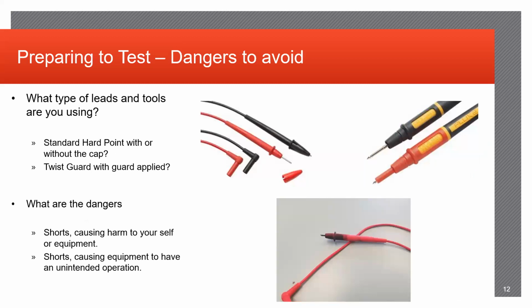Verifying correct test leads is important, especially when you're hooking up with your meter. The picture shown on the very right is a standard Fluke lead. The top black lead is actually much more dangerous than the bottom red lead, and the reason is that the metal piece on the black test lead shows much more surface area. When you're measuring live voltages, especially DC or AC, it could cause a short from one terminal block to the next, or even a short if your finger's close enough to it, straight from you to ground, which will cause either injury or even worse. So correctly identifying that the leads are insulated, secured, and properly handled is extremely important when testing live voltages.